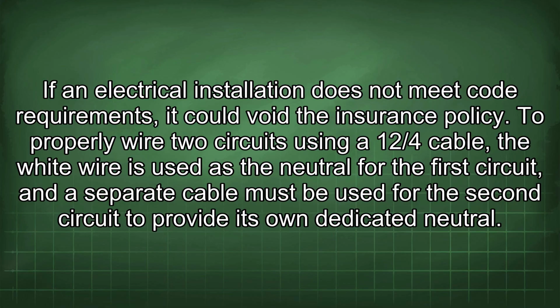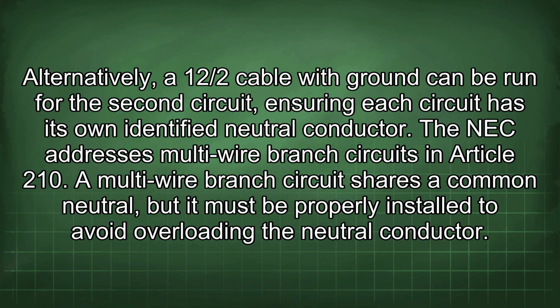To properly wire two circuits using a 12/4 cable, the white wire is used as the neutral for the first circuit, and a separate cable must be used for the second circuit to provide its own dedicated neutral. Alternatively, a 12/2 cable with ground can be run for the second circuit, ensuring each circuit has its own identified neutral conductor. The NEC addresses multi-wire branch circuits in Article 210.